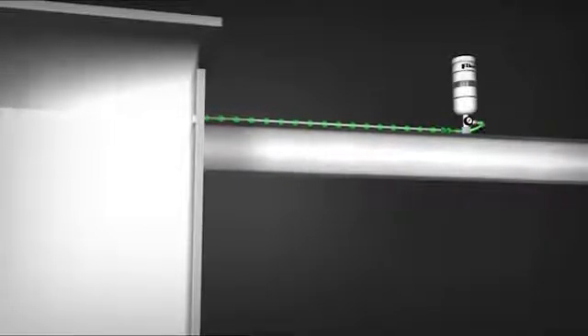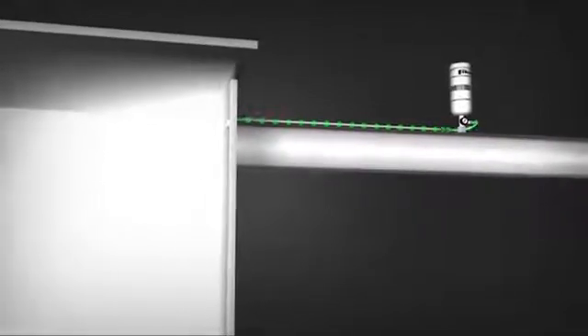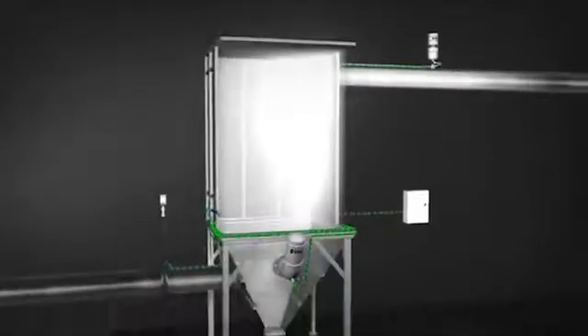The system uses 500 PSI of nitrogen to drive suppressant into the ductwork, providing a chemical isolation barrier that prevents the propagation of the explosion.